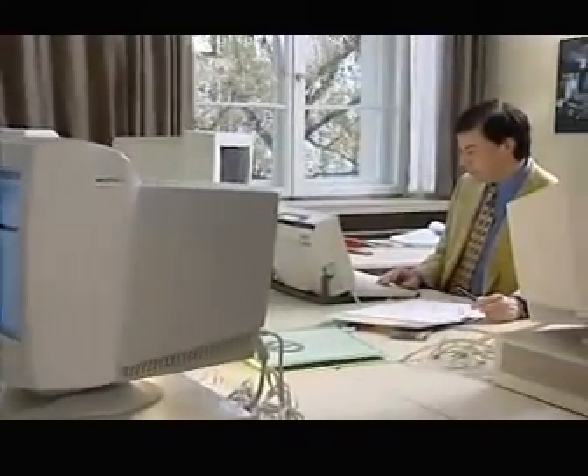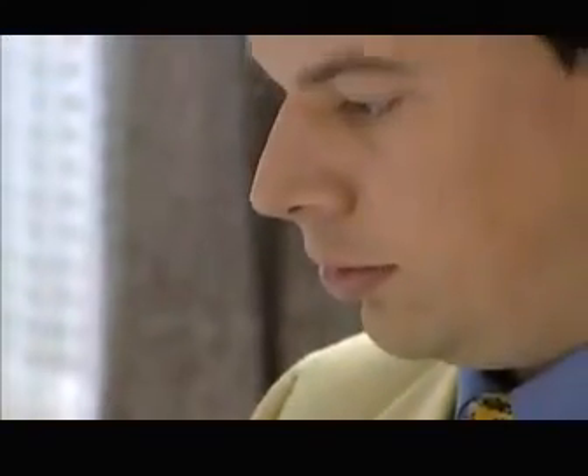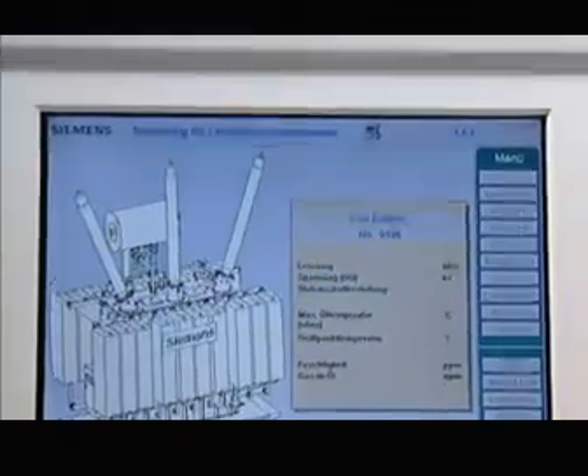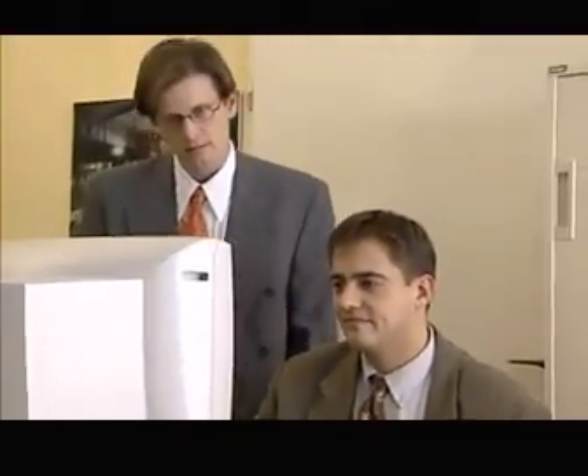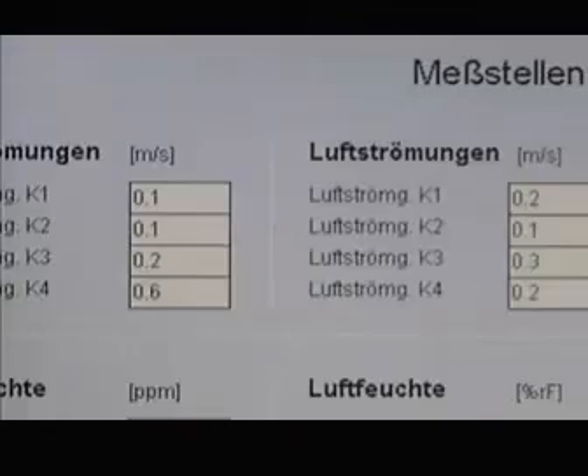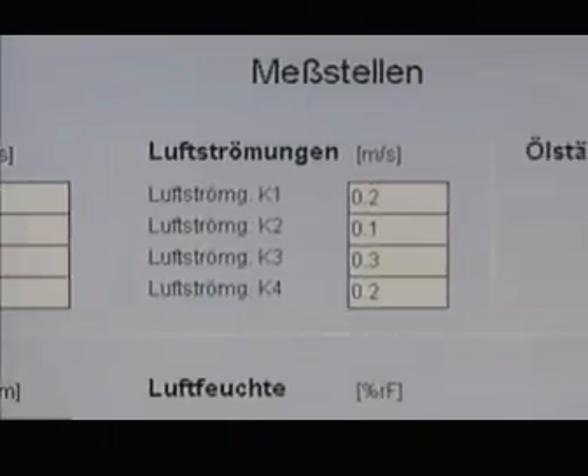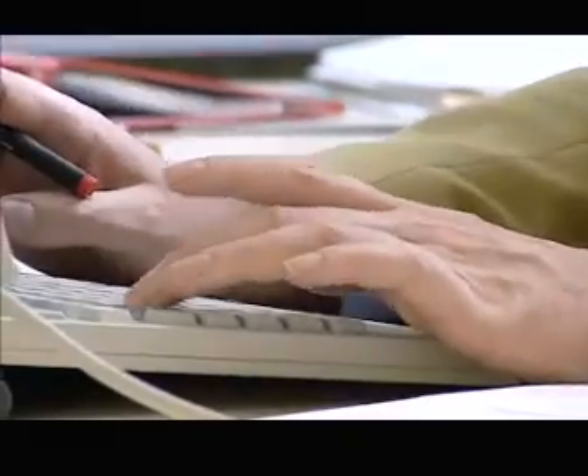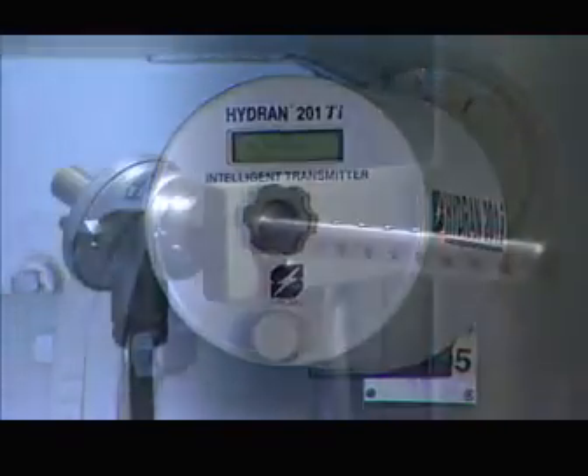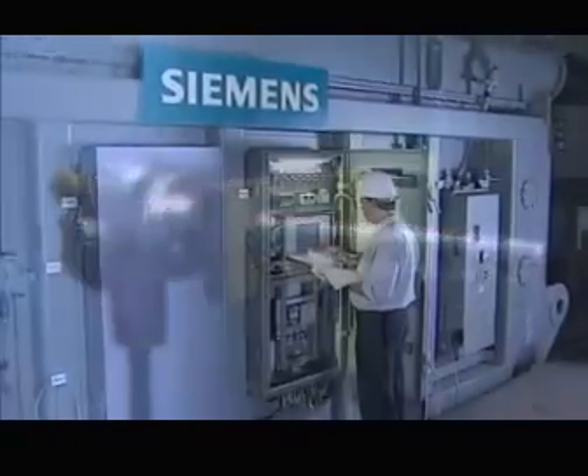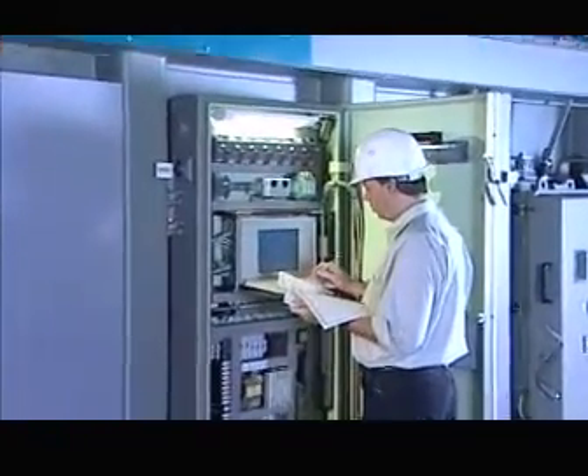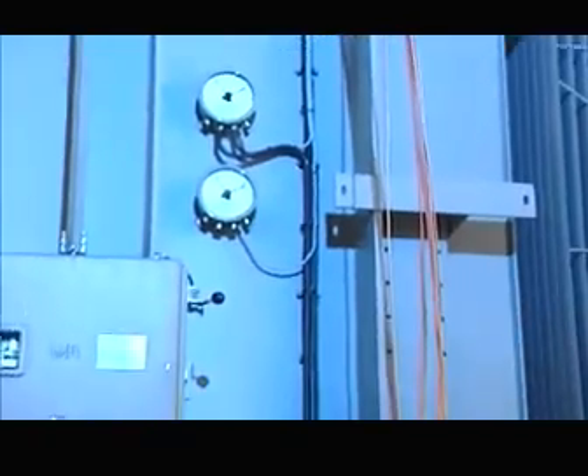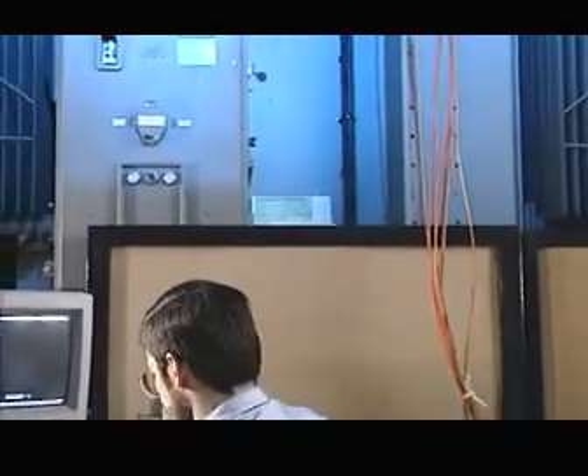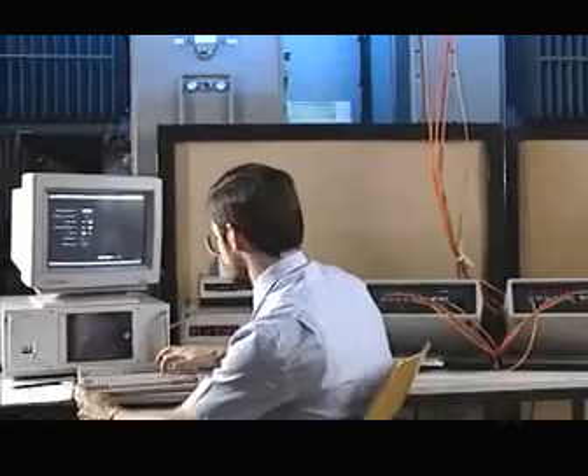Siemens monitoring. Our engineers are always coming up with bright ideas. If our customers request it, we equip our transformers with our new monitoring system. The principle is to move away from regular maintenance intervals to maintenance on demand. That saves operating costs. For example, using fiber optic methods, we can even measure the temperature at the center of a winding.